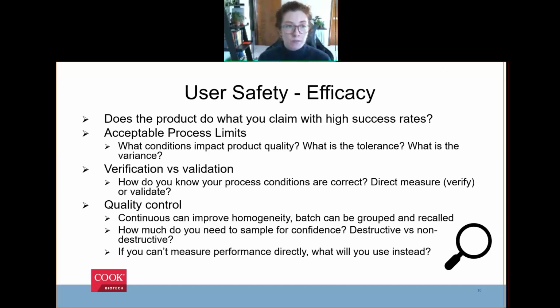We also start to consider our process verification and validation. So verification is when you measure something directly to ensure that it has a quality that you're looking for. So volume: if I pour some amount into a tube and I can see, oh, it's 50 mils, I'm verifying visually that it's 50 mils. You can verify mass on a scale. You can verify temperature with a probe. If you can design a process for something to be verified, that's usually the better way to go.